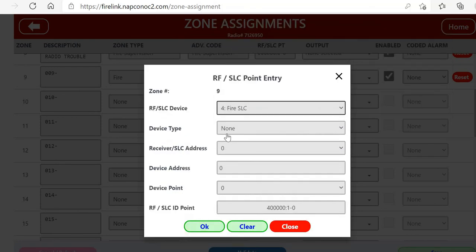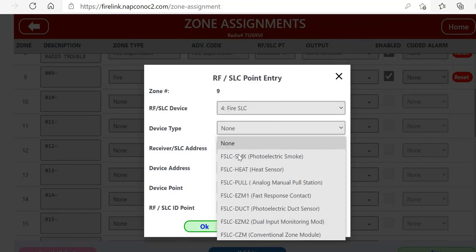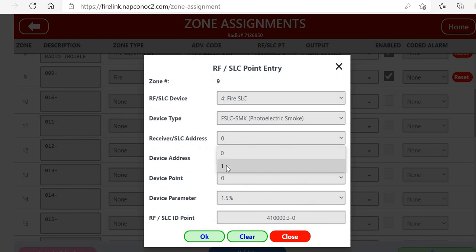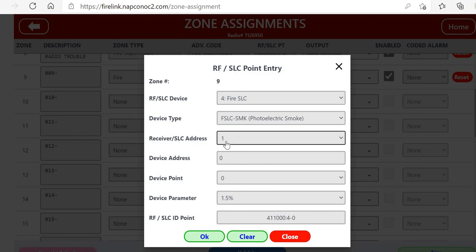Then we're going to have to put in the RFSLC point address. So we click on that and the screen will come up. We're going to pick Fire SLC. The device type, we're going to make this a smoke. The receiver or SLC address, which is our SLC card, which we made number one.